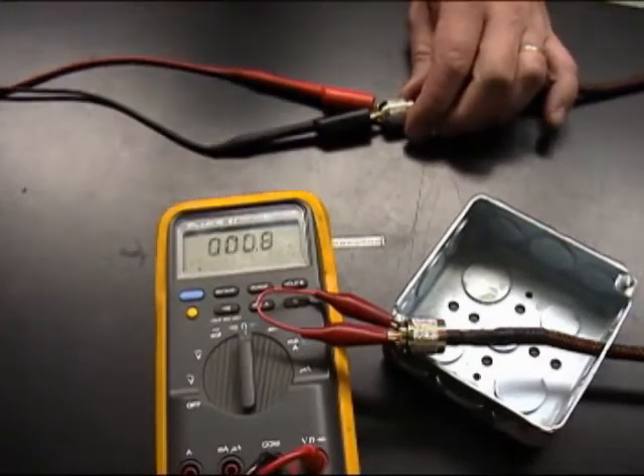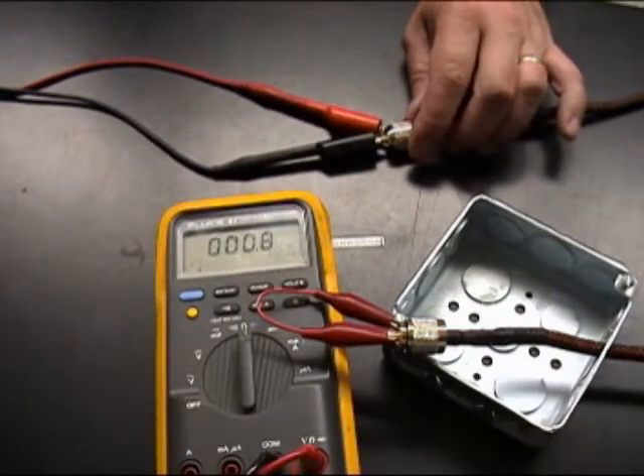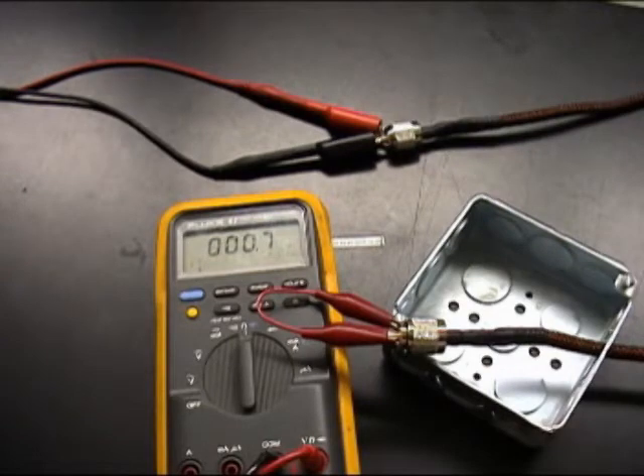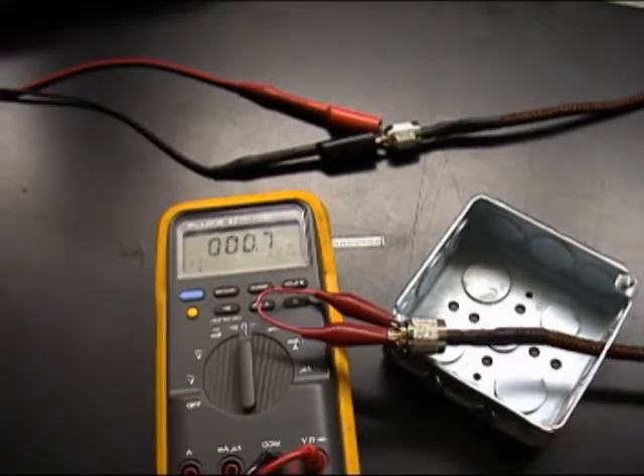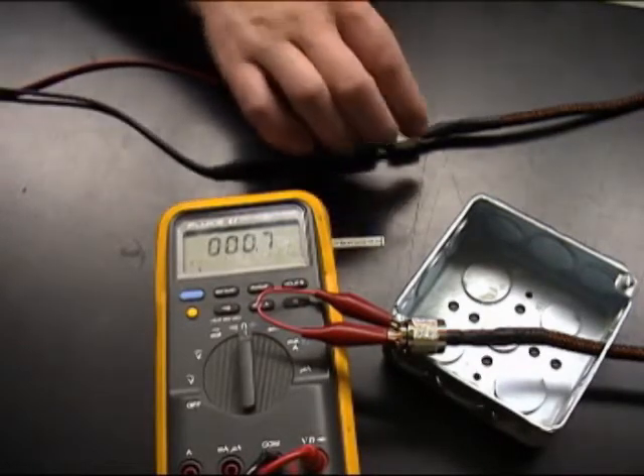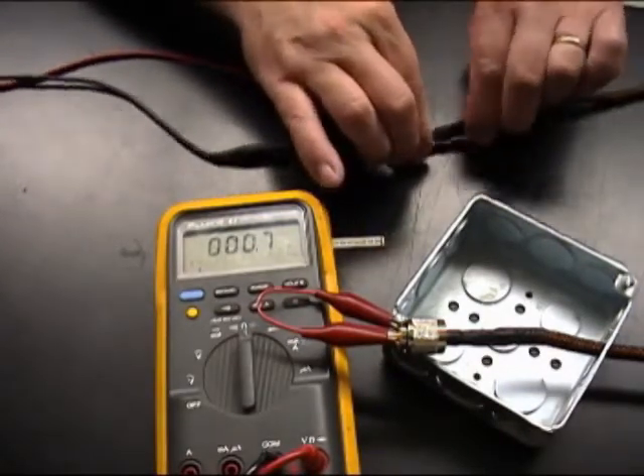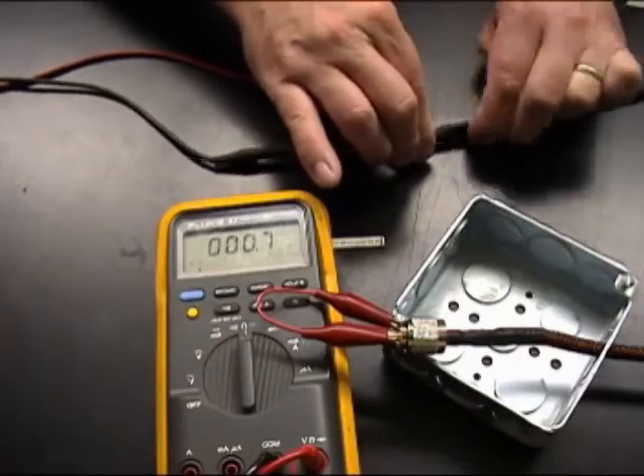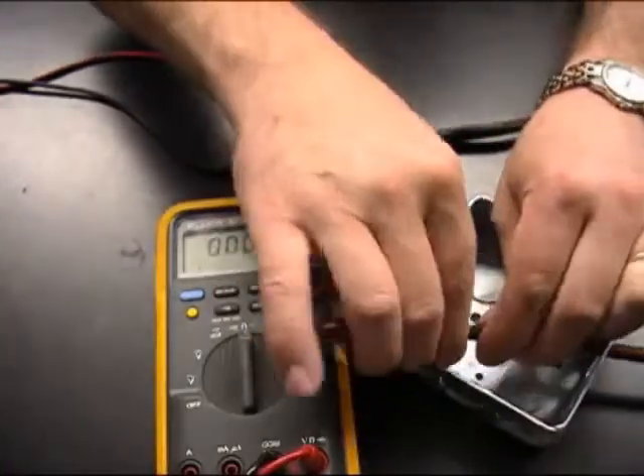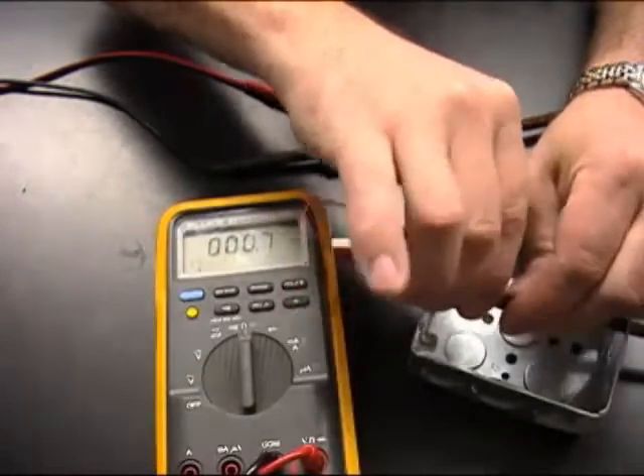For a good continuity reading, you should read approximately 10 ohms per 1,000 feet of cable. For this cable, we are reading less than 1 ohm. If, when we flex the cable at the connectors on both sides of the cable, the reading stays stable, the connector passes the continuity test.